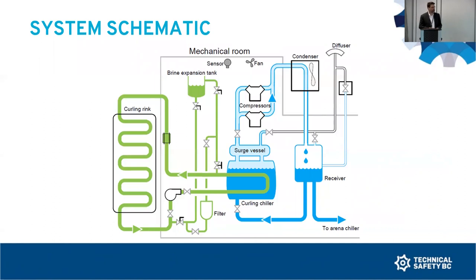So what had occurred is saturation of the brine from the ammonia leaking in occurred in and around the hole. And in response to, as I mentioned the night before, a leak that was detected at about 4 a.m. where ammonia was leaking out of the brine expansion tank, a number of valves were closed by the operator and the first responders to that incident. Effectively, in order to address the leak, they closed off the brine system valves, isolating the brine system. But they also isolated the curling chiller, knowing that there was a breach in there, in order to protect the rest of the system.